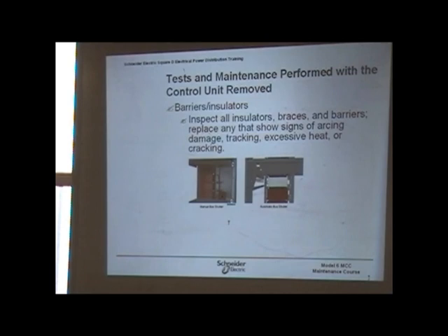And this, along with the I-line and Masterpacts, were designed at the time when we were doing this so that you could actually take this out with the bus being energized, right? Your main is closed, so everything is energized at the top, and your horizontal buses, along with the vertical buses, are energized. So once you disconnected, of course making sure the breaker or your disconnect was open and you checked it, you take your T leads off and you'd be able to pull it out.